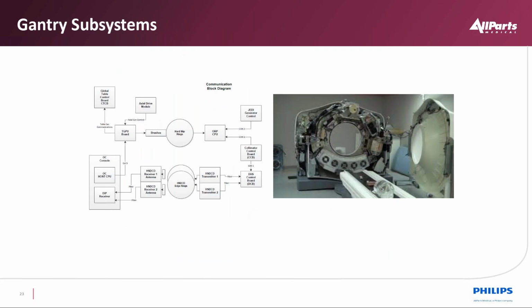So this goes into more of a flow perspective of how we're moving the data and the control. So we're using slip rings to communicate as this gantry rotates, and this gantry will do 0.35 seconds. So it's very fast for cardiac runs. It's a 64 slice system. So this system was released to the market 20 years ago in 2005. So still viable today. There are still installed systems with regards to that.